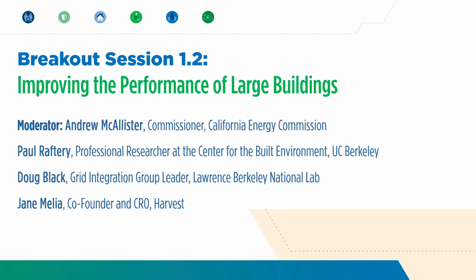When you think about large buildings like hospitals or large offices, most existing buildings are designed around really high water temperatures for heating. Even on a mild day, they need relatively high temperature water, and that poses a big challenge for retrofitting them cost effectively, because unless you're gutting the building as part of your retrofit, at which point it's basically new construction, you have to ask: do they actually need that high temperature hot water, or are there a lot of uses for which they need to mix it down? For space heating, in some older buildings the coils in the VAV boxes in this room would be sized for 180-degree water. In a lot of climates there's a lot of oversizing, so you could probably get away with maybe 150, or even 140, but that's a challenge for a lot of the existing heat pumps on the market. It depends on the type of existing building.